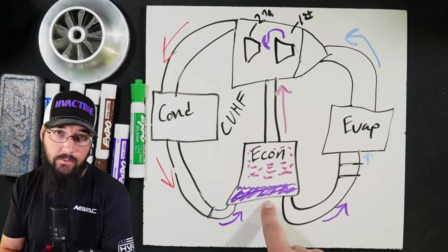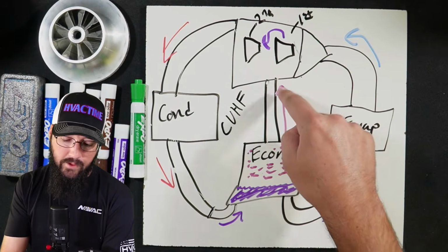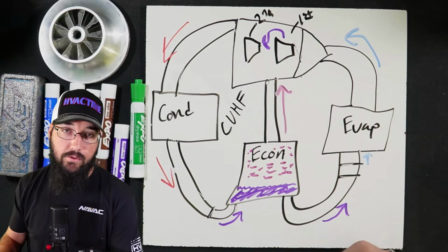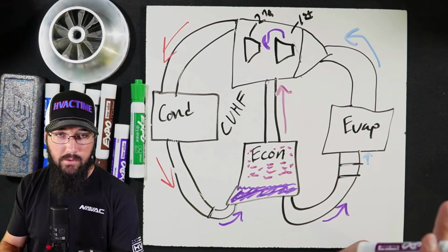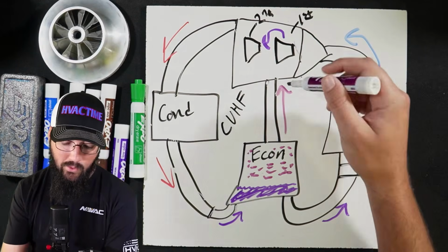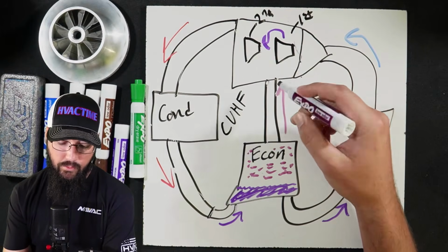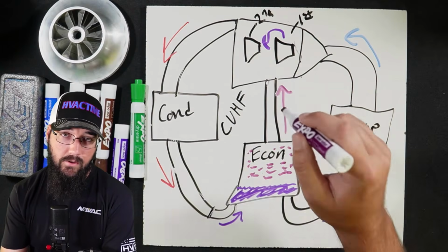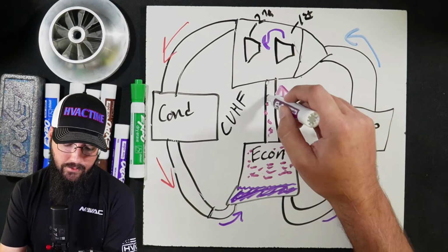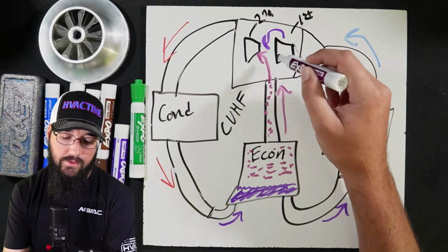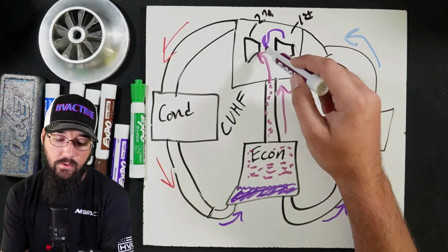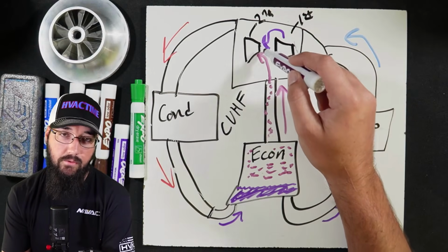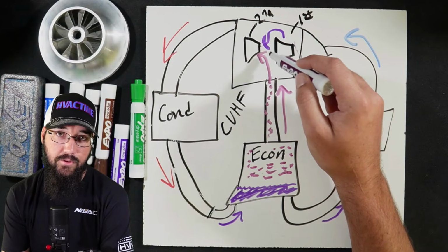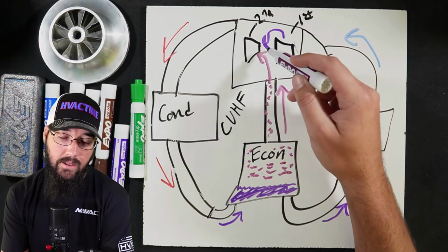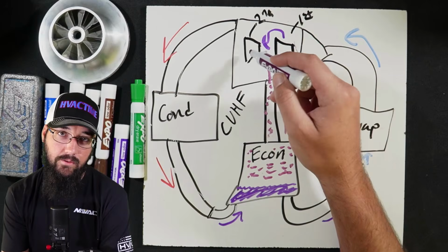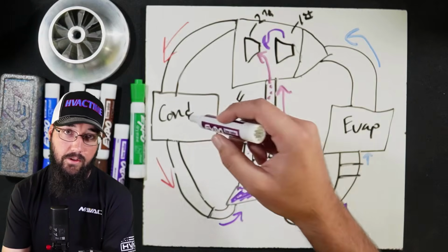So we've got this standing liquid here in the bottom of the economizer. We've got this vapor, which I show goes back up into the impeller. Two things are happening in this process. Let's show both of them. On one hand, we are reducing the load on the compressor because this vapor gets drawn up into the second stage impeller, where we also have a medium pressure state coming in from the first stage. So these two refrigerant streams mix right here, and they enter into the final, or second stage impeller, and then get turned into hot gas.